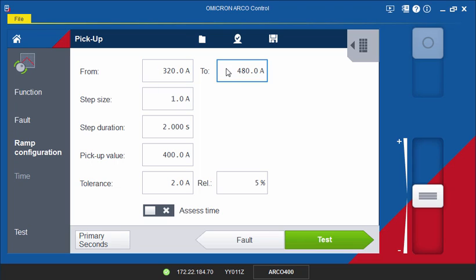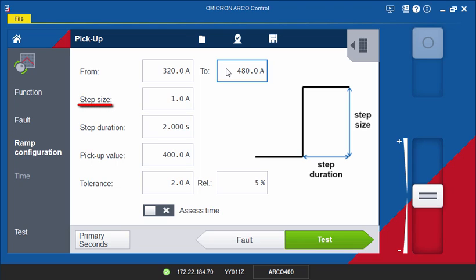The amplitude of the step size is a compromise between accuracy and test time. The bigger it is, the less accurate and the shorter test time. If you choose a value larger than the tolerance band, the resulting measurement will be of no use. As a reference, we recommend that you divide the tolerance by 4 as the step size magnitude. So, 5% of 400 amps divided by 4 makes 5 amps.